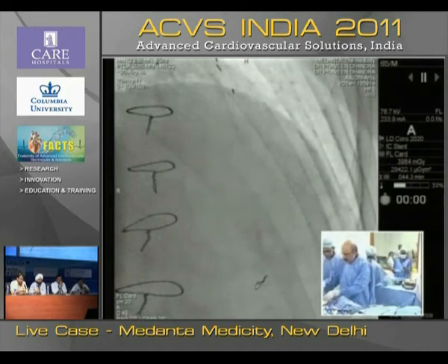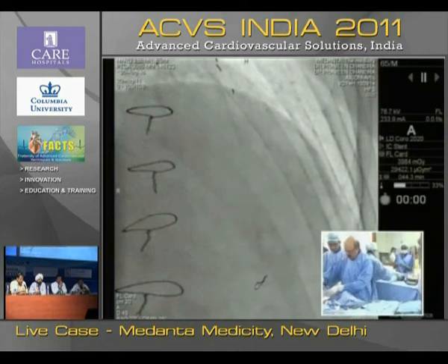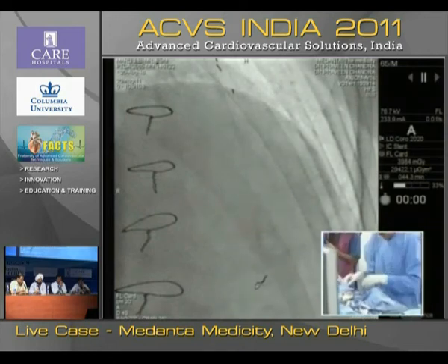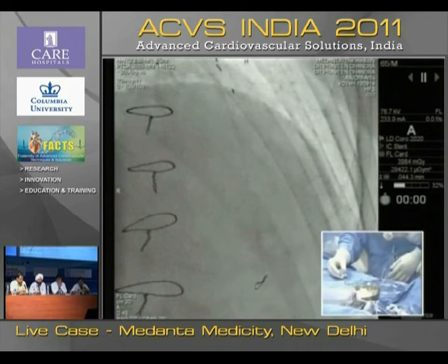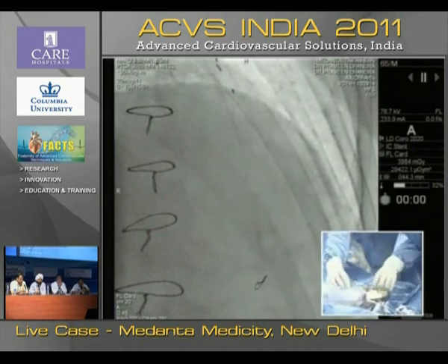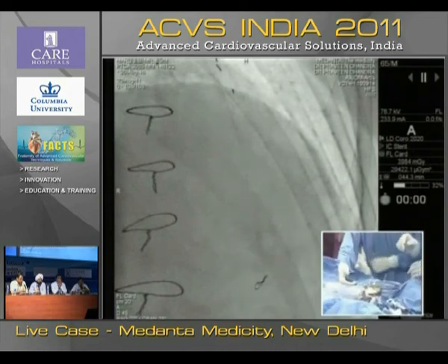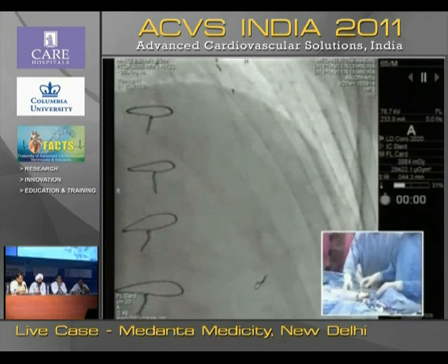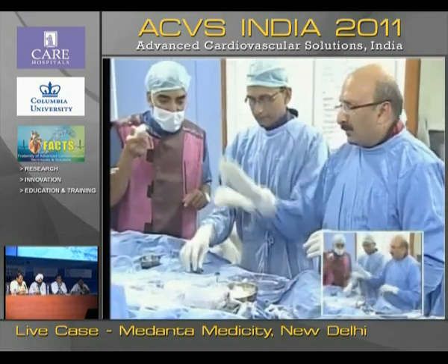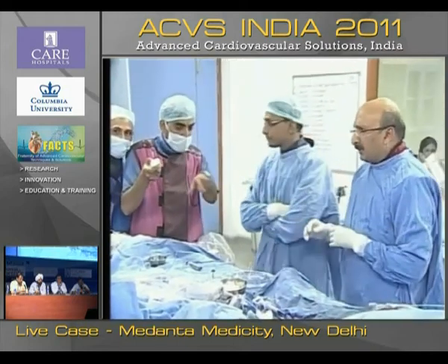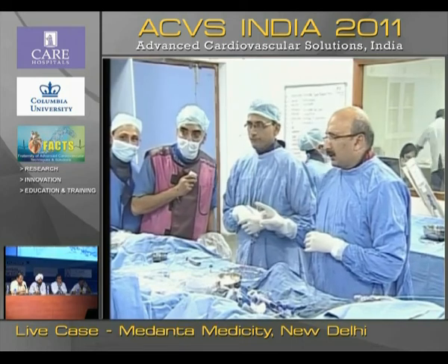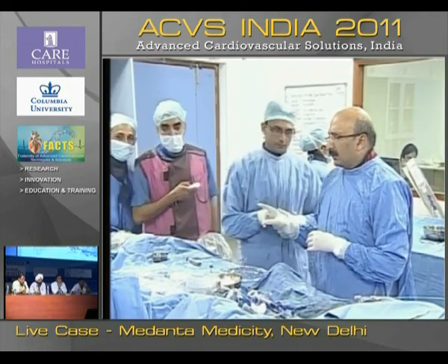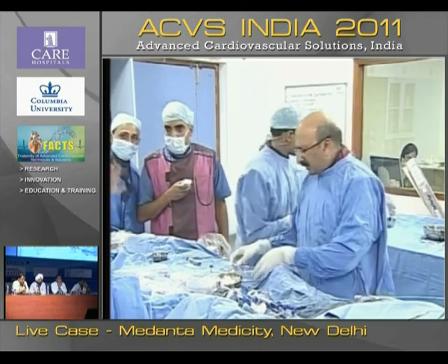So we are preparing the wire. First push some saline, and now take this. We are connecting this lead to the monitor here, which is in front of us, and now we have the pressures on this monitor, and now we are calibrating the wire. So the wire is being calibrated first. Okay, calibration, it says okay. So we are ready to take the wire.